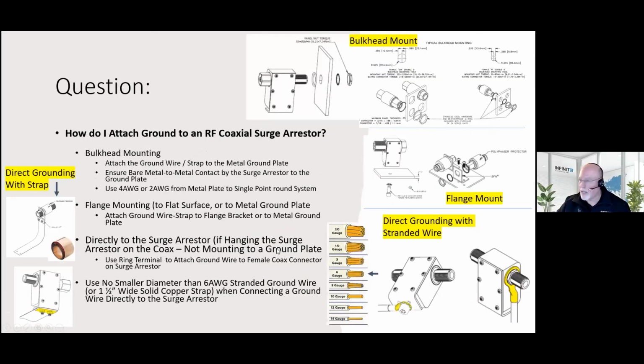Okay, how do I attach ground to a coaxial surge arrestor? It depends on whether it's going to be bulkhead mounted or flange mounted. If it's bulkhead mounted and that's a metal ground plate, then the ground wire goes to the plate. If you're flange mounting it to a flange bracket and then to a plate, then again, the ground wire goes to the plate. Or if the plate here is attached to something non-metallic, you could attach the ground wire to the plate or that bracket.